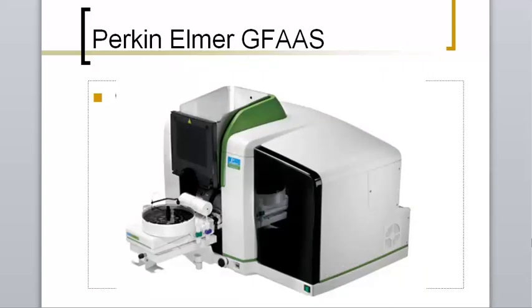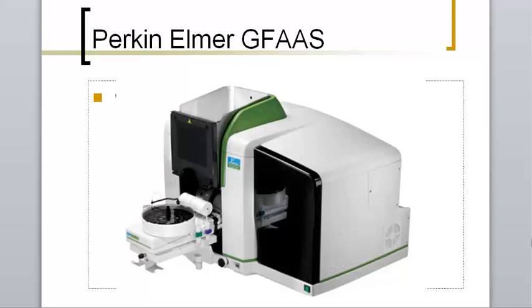Here's an overall picture of the Perkin Elmer Graphite Furnace AA, and this graphite furnace you can't really see, but the take-home message here is that these AA systems look very similar to all the other AA systems that might be sitting on the shelf. The only difference is the piece that goes into the sample compartment - is it a burner head or is it a closed container that we call the oven or the graphite furnace? Here you kind of see an autosampler tray that's sitting in front that will take the sample up and shoot it inside of the machine to get some measurements with. So that's the story with graphite furnace.